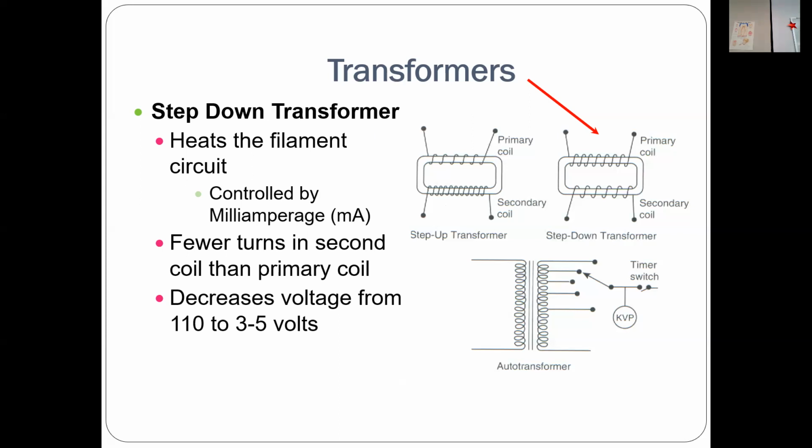Okay, this is a weird question. I might even answer it when I ask it. When you turn on the power at the beginning of the day, does that start making the electron cloud, or is it when you push the button? No, it's when you flip on the switch. At the beginning of the day, you flip on the switch to turn your unit on, and immediately you start to create an electron cloud. They're totally ready and just sitting there bubbling off the tungsten filament. The tungsten filament is where the electron cloud is, and they're just boiling off of it, waiting to go somewhere. Then when you push the button, you accelerate them and get them to where they need to be.